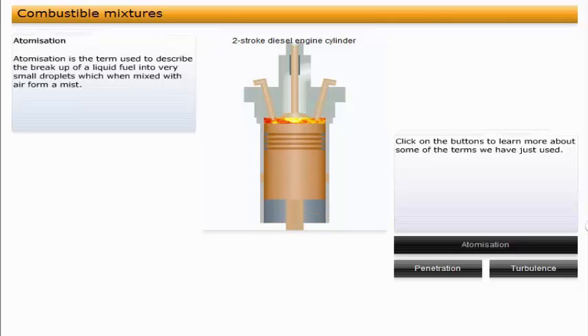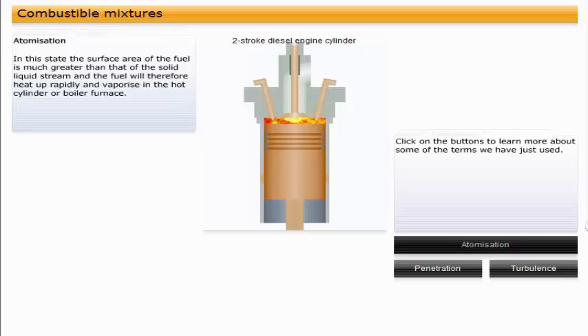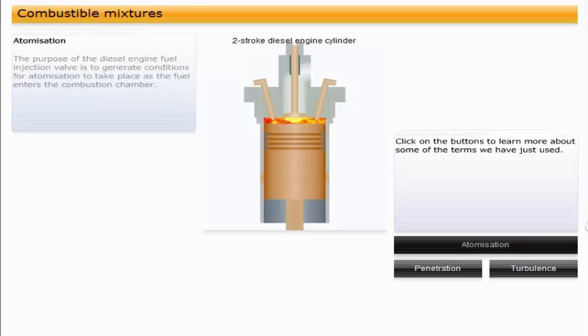Atomization is the term used to describe the breakup of a liquid fuel into very small droplets, which when mixed with air form a mist. In this state, the surface area of the fuel is much greater than that of the solid liquid stream, and the fuel will therefore heat up rapidly and vaporize in the hot cylinder or boiler furnace. The purpose of the diesel engine fuel injection valve is to generate conditions for atomization to take place as the fuel enters the combustion chamber. Similarly, a boiler burner tip will help create the conditions for atomization, often using compressed air or steam to assist the process.